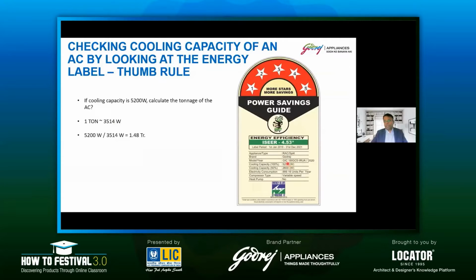If you see this label, the cooling capacity is mentioned—this is a clear denotation so the customer has visibility of the exact capacity of the product. If it's 5,200 watts here, and you calculate it on 3514, you come to know the exact capacity is also 1.48 ton.